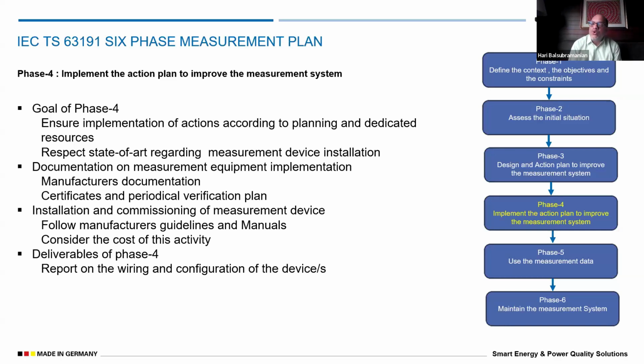Ultimately, whoever you're buying these devices from, follow the manufacturer guidelines and manuals clearly. Generally, many customers do not read manuals - they think if I know S1 and S2, I can just connect the CTs, and if I have V1, V2, V3, I connect the voltages and it's done. But it's always better to understand the manual, which helps in doing this properly. This is one of the criteria in this phase - reading the manuals itself, so we can understand the product perfectly and get as much benefit as possible from it. That's very important. Nowadays electronics has improved so well that we can do much more than what we are currently doing with these devices.